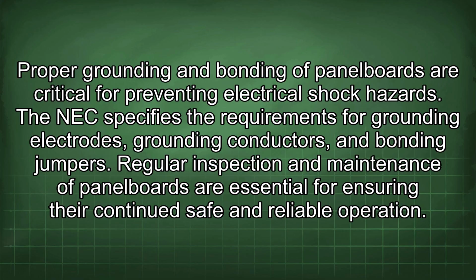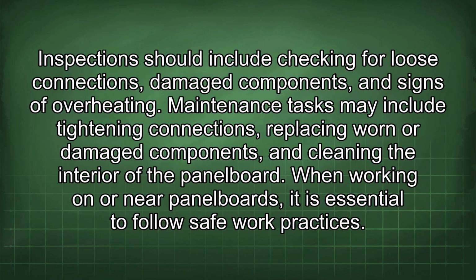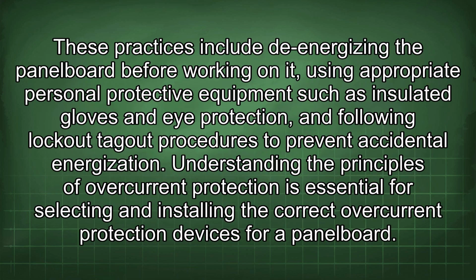Regular inspection and maintenance of panelboards are essential for ensuring their continued safe and reliable operation. Inspections should include checking for loose connections, damaged components, and signs of overheating. Maintenance tasks may include tightening connections, replacing worn or damaged components, and cleaning the interior of the panelboard. When working on or near panelboards, it is essential to follow safe work practices. These practices include de-energizing the panelboard before working on it, using appropriate personal protective equipment such as insulated gloves and eye protection, and following lockout-tagout procedures to prevent accidental energization.